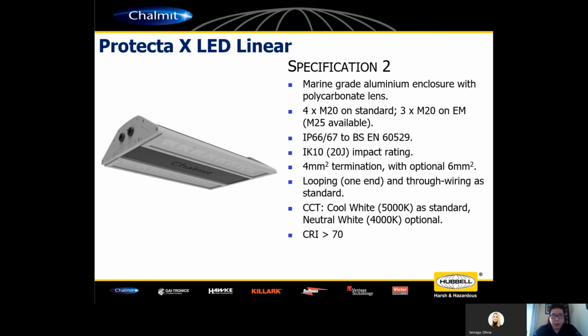Marine grade aluminium enclosure - the product is fully metallic. The only plastic visible from the outside is the polycarbonate diffusers on the wings, a clear polycarbonate lens. As standard for the non-emergency product, you'll have 4 times M20, but on the emergency version one of those cable entries is given up to the battery stick, which I'll show you more later. Bear in mind M25 is also available as a selectable option.